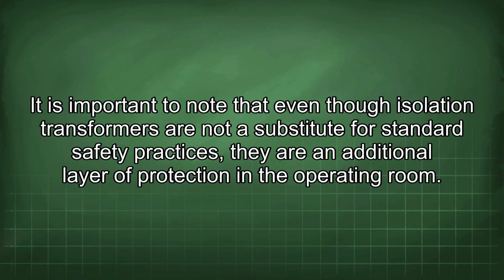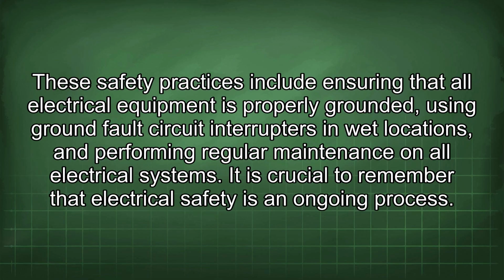It is important to note that even though isolation transformers are not a substitute for standard safety practices, they are an additional layer of protection in the operating room. These safety practices include ensuring that all electrical equipment is properly grounded, using ground fault circuit interrupters in wet locations, and performing regular maintenance on all electrical systems.